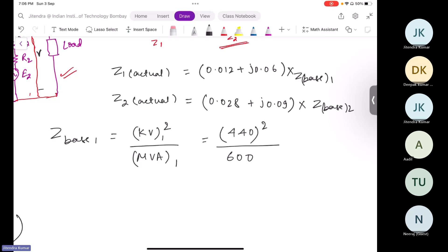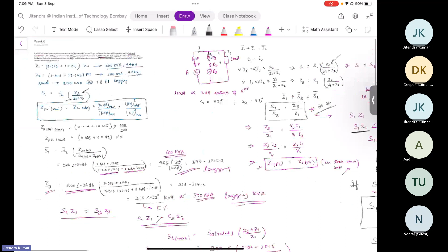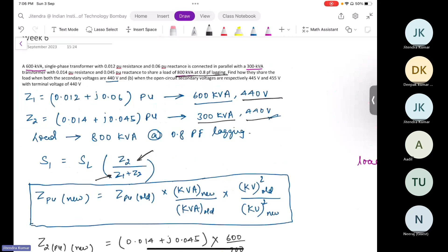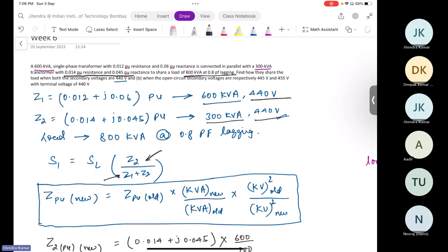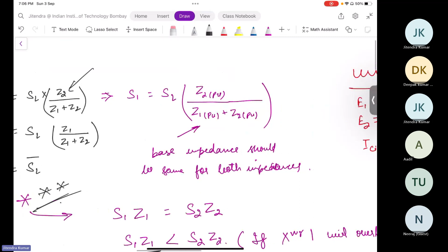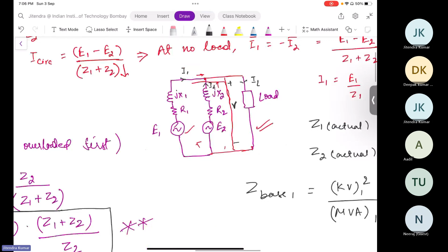Do we need to compute at its own base or the same base? Because if it will be their own basis, then I don't find anything here. Let me confirm it from the expression. So this 0.014 per unit of resistance with 0.045 per unit of reactance — we have to compute at 600 kVA, right? Why is this happening? Because we had to convert at the same value of base in part A. So here also we want to convert the actual value with the same base, the higher base, such that we avoid this number.